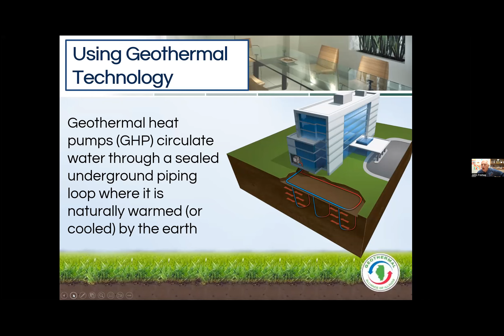This is a really important slide—look at this. Where I am in Springfield, Illinois, our Earth temperatures are typically about 54 to 55 degrees. Probably in northern Illinois, in the Chicagoland region, I'd guess about 52 degrees. My incoming water temperatures are always between 54 and 55 degrees. I'm about 8 feet from my geothermal indoor unit right now—you probably can't hear it, but I'm very close. If I walked over to my flow center, it would tell me my incoming water temperature is somewhere in the low 50s.